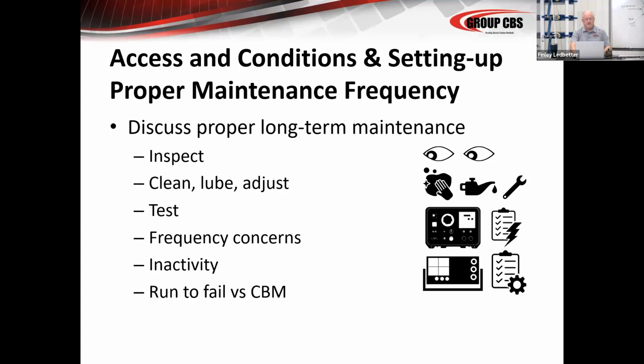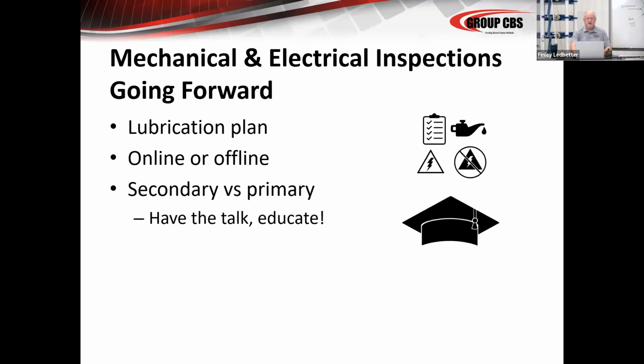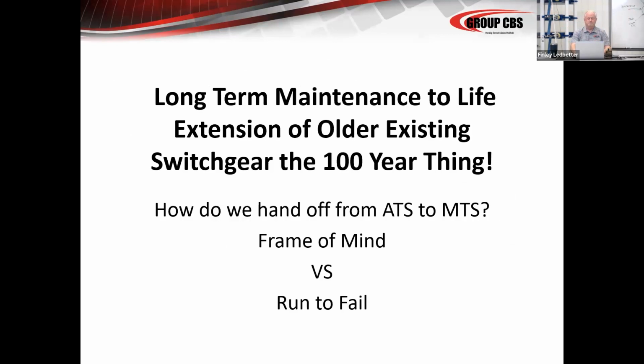Basically, is this a run-to-fail application or a situation where they're actually paying attention to some sort of condition-based maintenance? Have a good lubrication plan, do online and offline testing, always secondary versus primary testing. Maybe you can do a secondary test somewhere in there and extend the primary testing, but we always recommend primary. Talk to the customer, educate the customer, be the smart guy in the room.